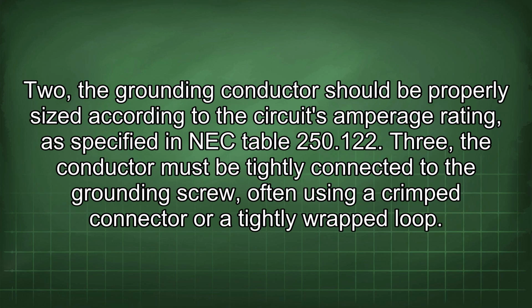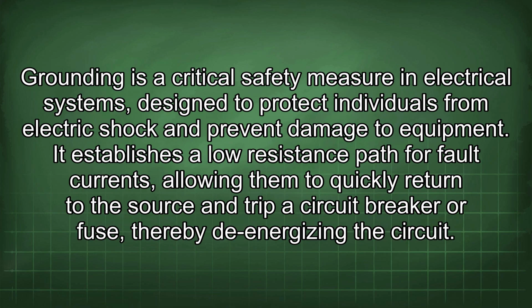The grounding conductor should be properly sized according to the circuit's amperage rating as specified in NEC Table 250.122. 3. The conductor must be tightly connected to the grounding screw, often using a crimped connector or a tightly wrapped loop. Grounding is a critical safety measure in electrical systems, designed to protect individuals from electric shock and prevent damage to equipment. It establishes a low resistance path for fault currents, allowing them to quickly return to the source and trip a circuit breaker or fuse, thereby de-energizing the circuit.